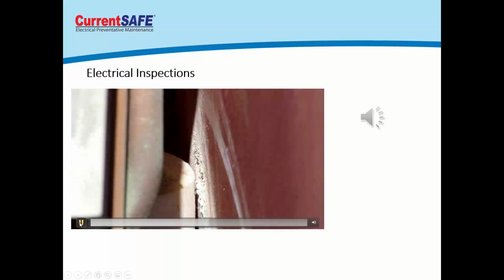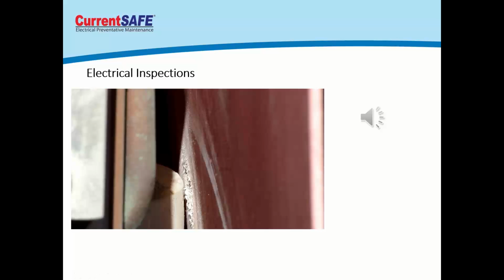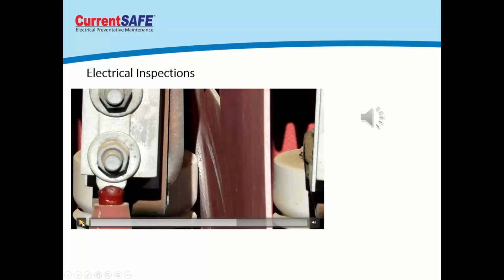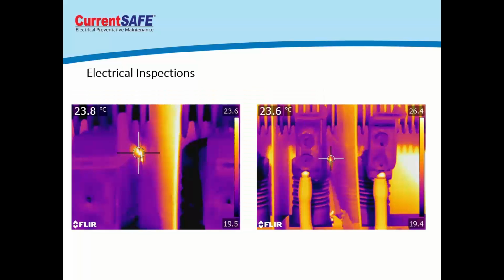You can see with that zoomed in like that, we took that with a live camera, meaning this is not ultrasonic detection that you're hearing. This is like a video camcorder, and we recorded that sound as we were zooming in. So that is an audible noise that you're hearing. So it has gone way past the ultrasonic early detection to a failure point. And that's why when we use the infrared camera, now we can see heat buildup in the distribution system.